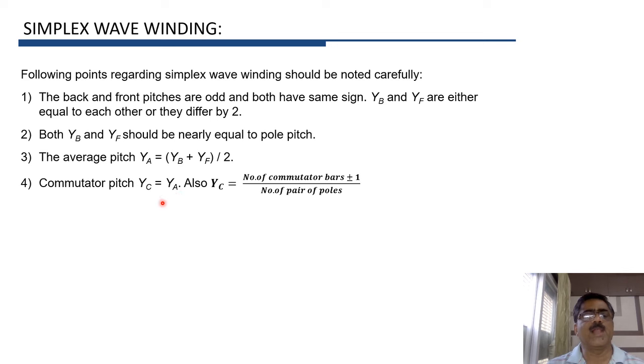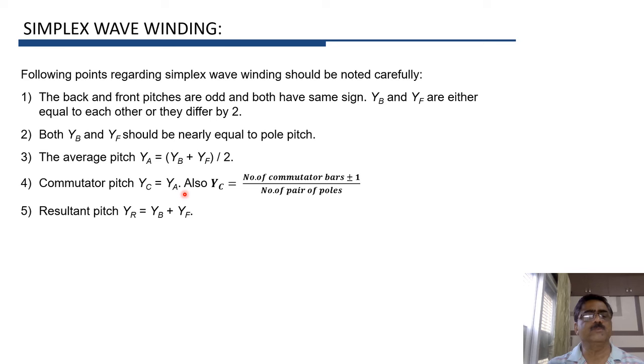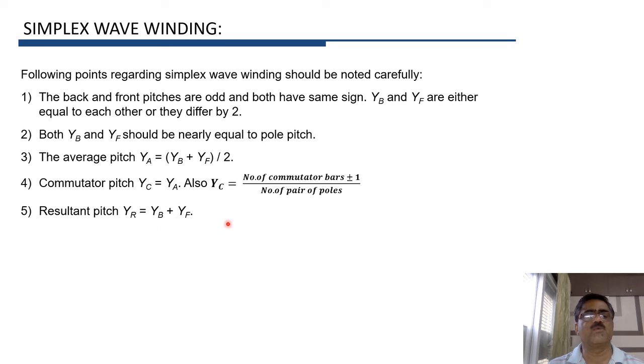In case of lap winding, which we have already studied, YC is equal to ±1. But in wave winding, YC is equal to YA. The resultant pitch YR in simplex wave winding is YB + YF, whereas in lap winding it is YB − YF.